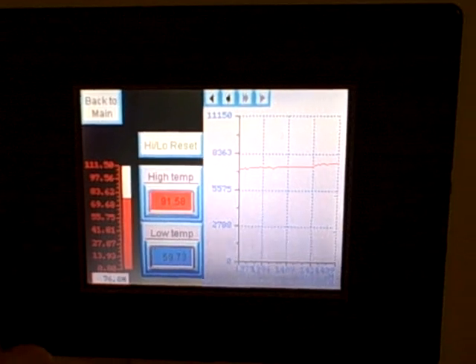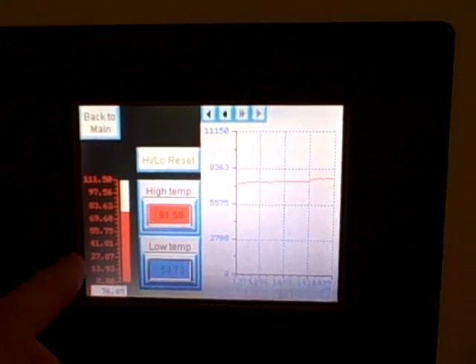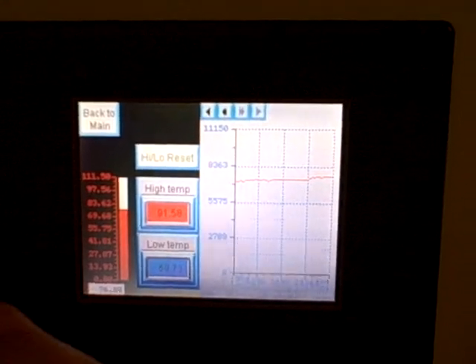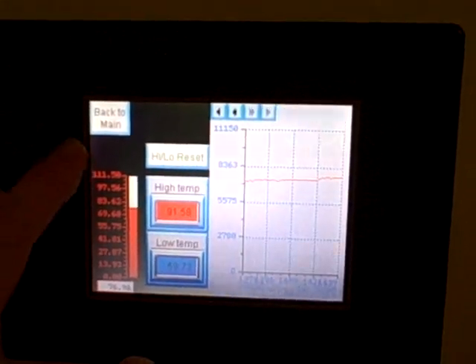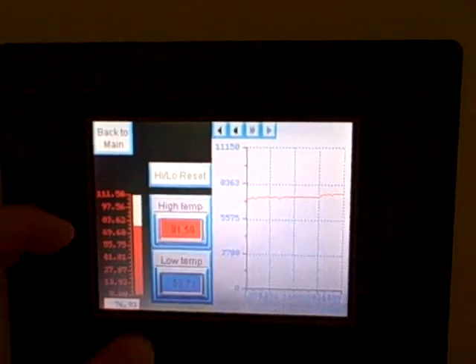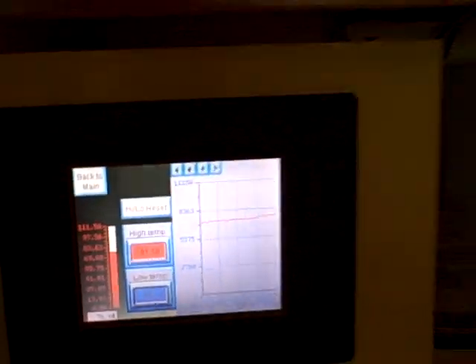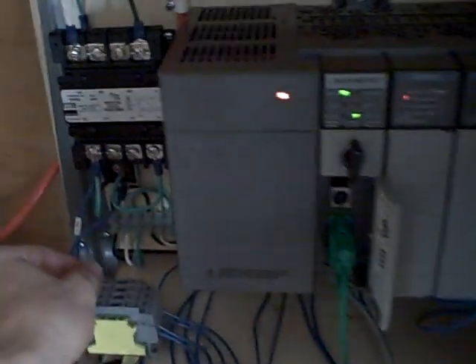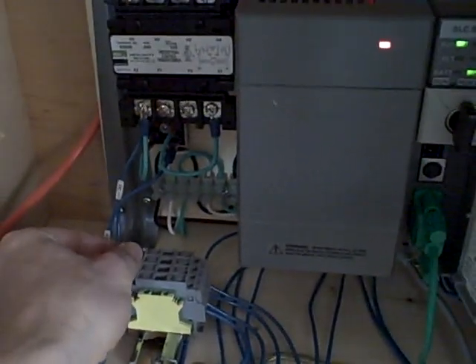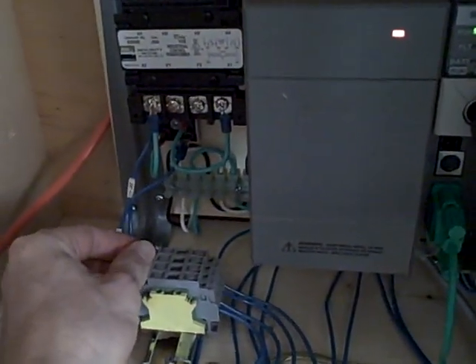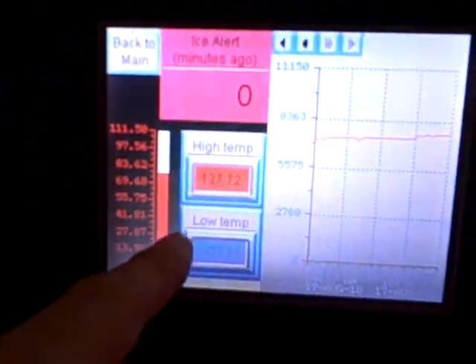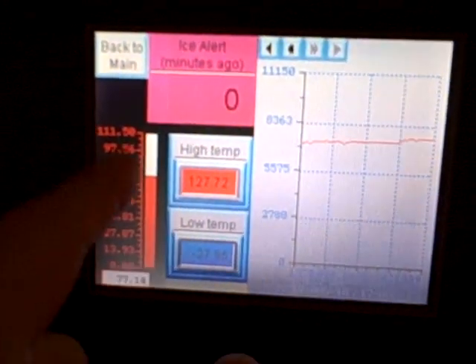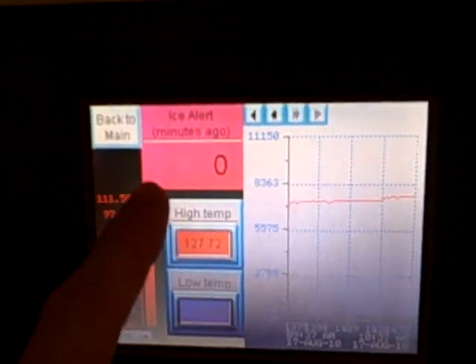If it drops below about 35 degrees, the ice alert will turn on. In fact I can demonstrate that right here. I can briefly disconnect the analog loop power and simulate a low temperature condition. And when I do that, we have right here an ice alert, and the ice alert has now gone away. The temperature has come back up, but it records how many minutes ago an ice alert happened.